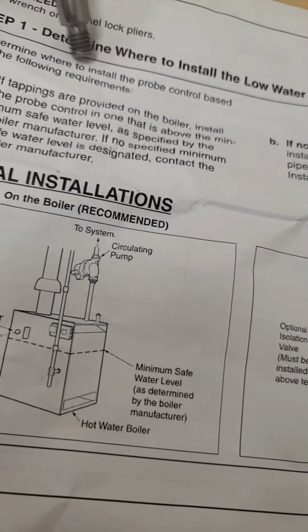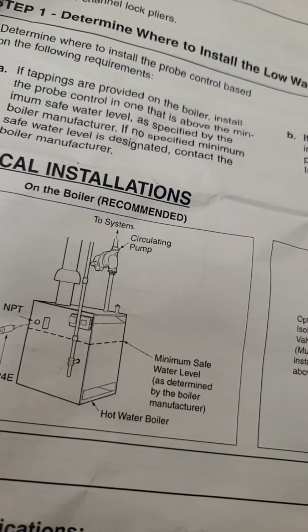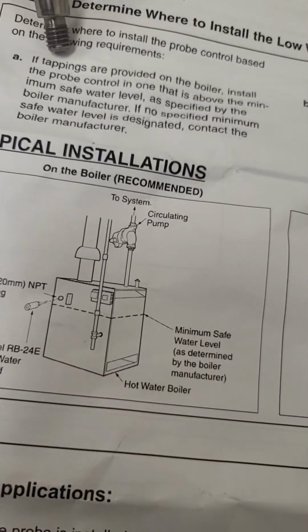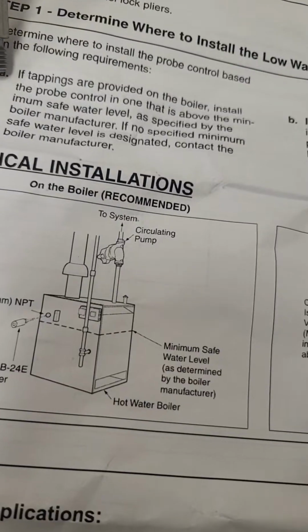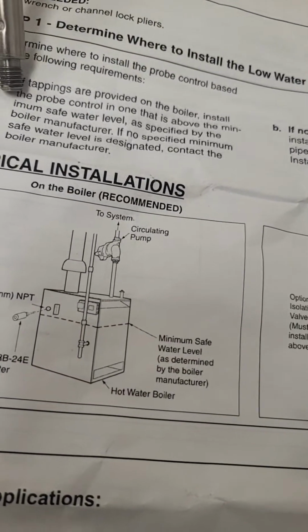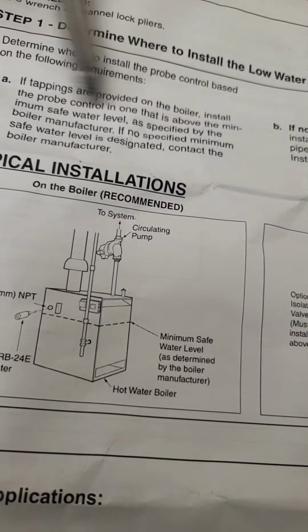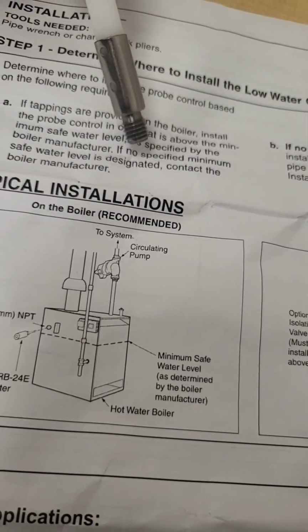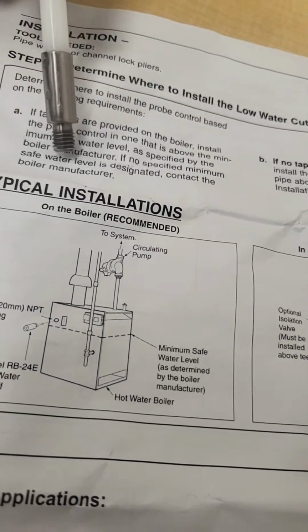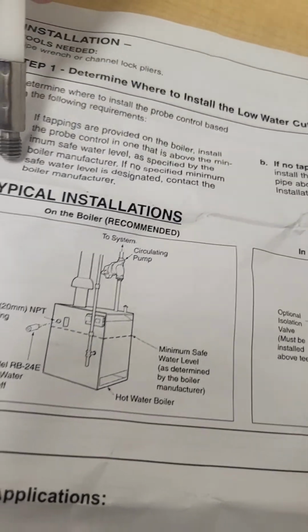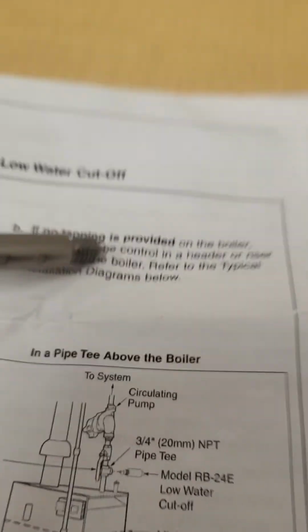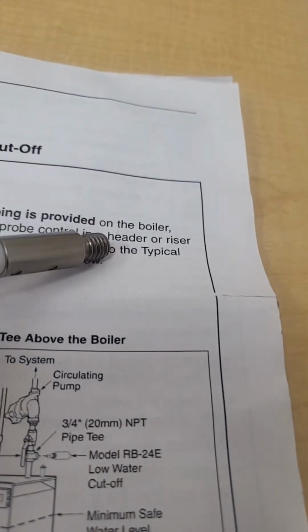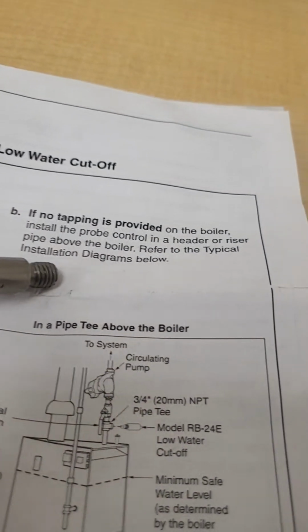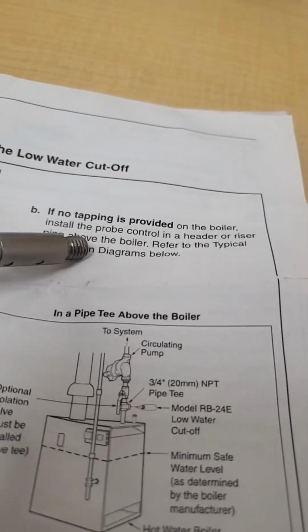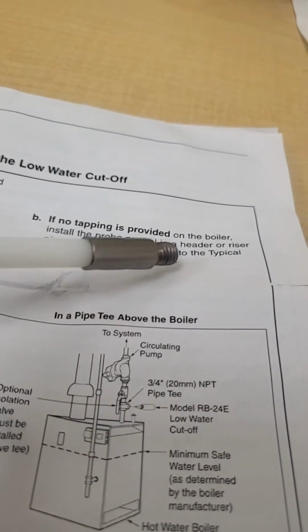Determining where to install the probe control based on the following requirements: A, if the tappings are provided on a boiler, install the probe control in one that is above the minimum safe water level as specified by the boiler manufacturer. If no specified minimum safe water level is designated, contact the boiler manufacturer. This is important: it tells you if no tapping is provided, install the probe on the header or riser pipe above the boiler. Make sure that the tapping is above the water level.